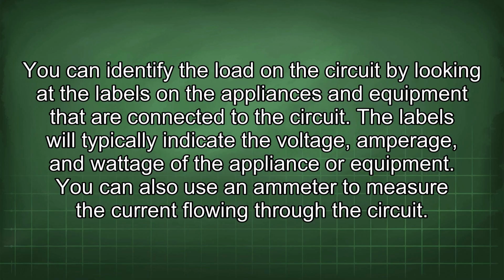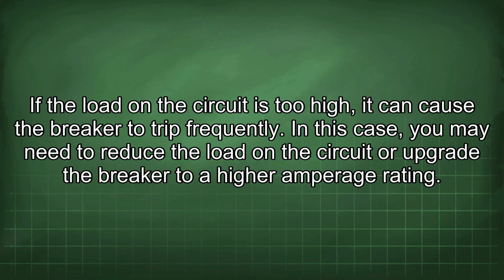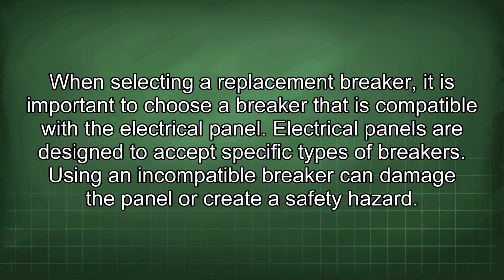You can also use an ammeter to measure the current flowing through the circuit. If the load in the circuit is too high, it can cause the breaker to trip frequently. In this case, you may need to reduce the load on the circuit or upgrade the breaker to a higher amperage rating.